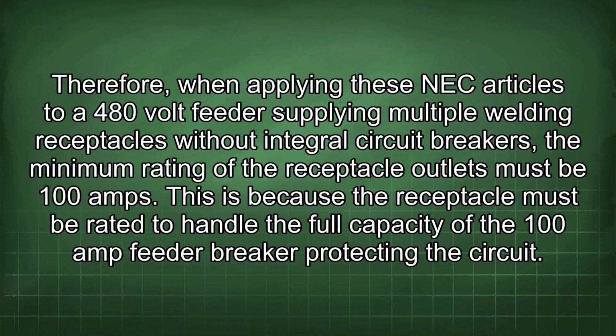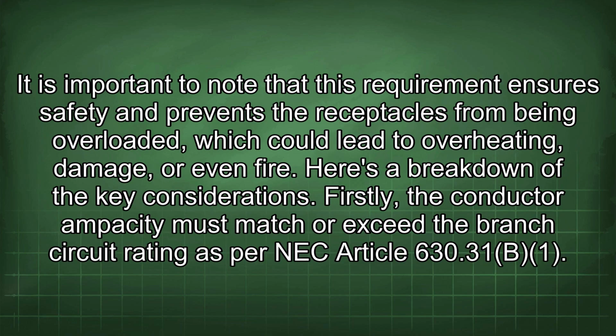Therefore, when applying these NEC articles to 480-volt feeders supplying multiple welding receptacles without integral circuit breakers, the minimum rating of the receptacle outlets must be 100 amps. This is because the receptacle must be rated to handle the full capacity of the 100 amp feeder breaker protecting the circuit. It is important to note that this requirement ensures safety and prevents the receptacles from being overloaded, which could lead to overheating, damage, or even fire.